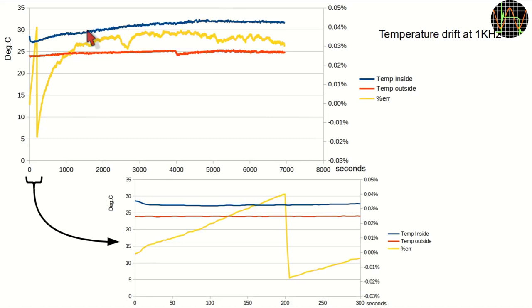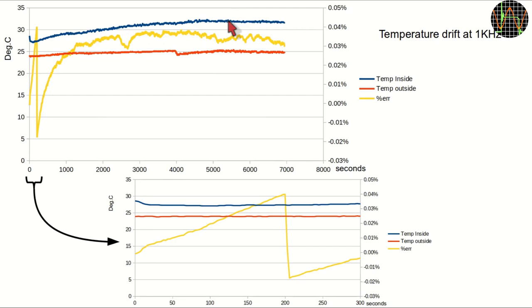The temperature inside the A201 is the blue trace and the room temperature is the red trace. The yellow trace is the error in percent against the selected 1kHz. First of all, I am quite pleased by the low drift and jitter over 2 hours which is better than the 0.1 spec and secondly I am relieved to see that the temperature inside stays quite reasonable despite the heat generated by all the electronics. The repair of the fan was obviously effective, at least for now.